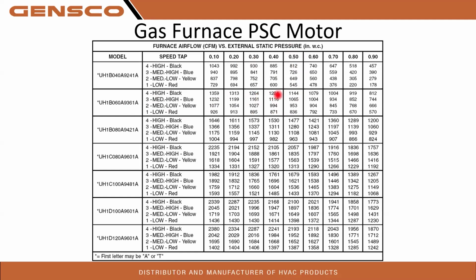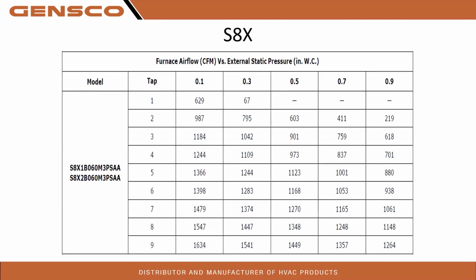So you can see we have to know our static pressure. Then we can move our speed taps to change on the different set of windings on that blower motor. And we got to constantly monitor our static pressure in order to confirm what our CFM is. But as the Department of Energy keeps pushing us toward everything more efficient, they'll probably do away with the PSC motors. There'll be some that still have it, but not used for airflow.